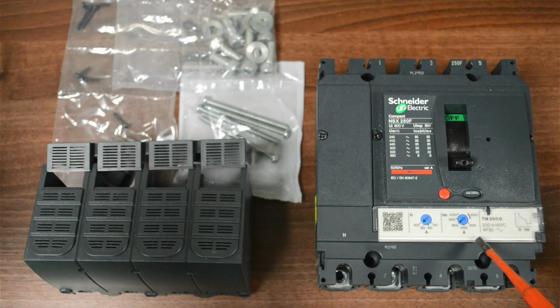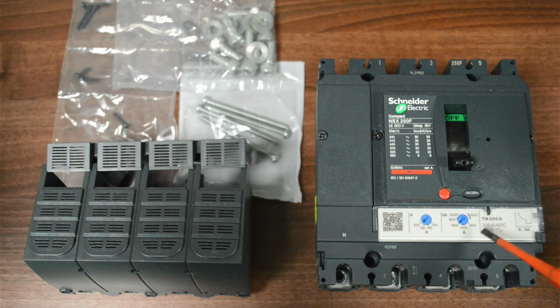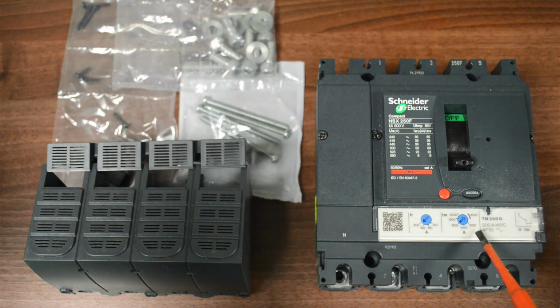Now the IM is the magnetic side of things, so that's looking at the short time magnetic setting. So this is a multiplier of the IR setting. It's often set between 1.5 to 10 times the value, and again you'll see here that we don't have that on this scale. It's actually specifically stating a value. So if you were setting it to 2000, for example, that would be the instantaneous magnetic effect of the MCCB, where if you had a dead short, for example, it's going to allow a faster or slower operation based on how you set this dial. And again, you can have them where there's time delayed sections on these as well, so you can offset the effect of the tripping characteristics of the device if it was to need a time delay on there as well.